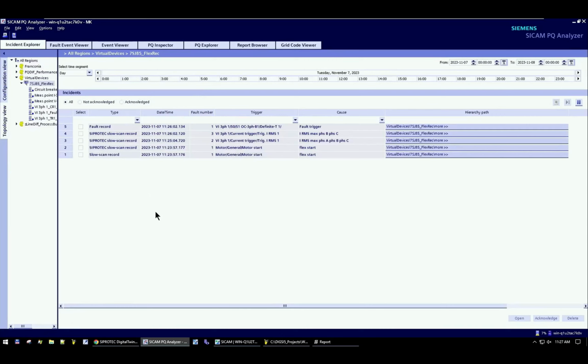We can see now that on the 7SJ85 flex record feeder, we have in sum 5 records. The first one here on the bottom was a slow scan record at this timestamp. This was fault number 1, and this was a motor start. This was an indication, or the binary signal, for the motor start we have tested in the digital twin.